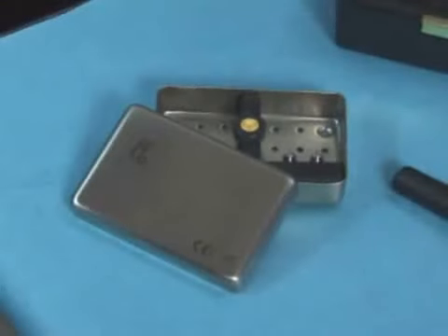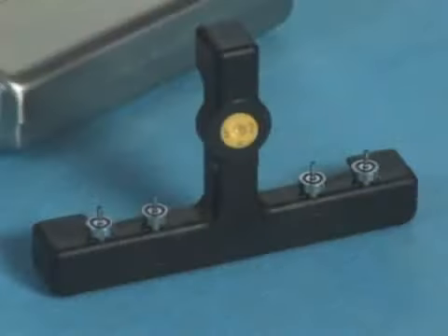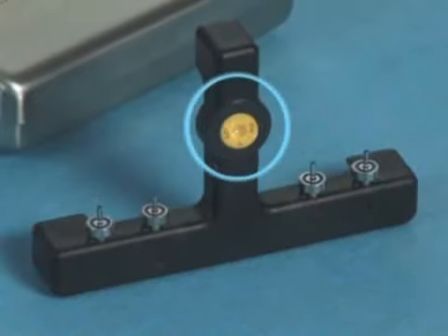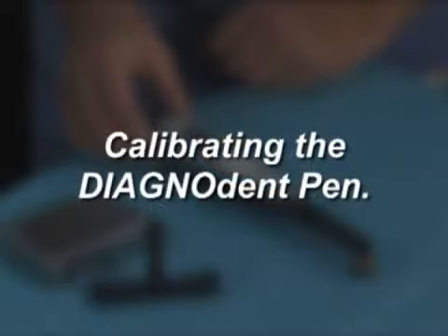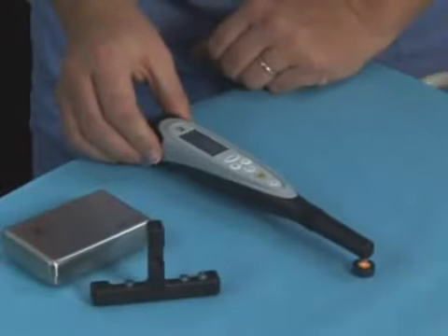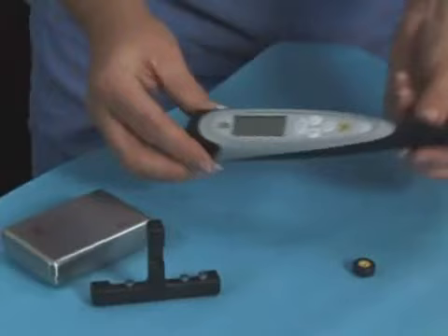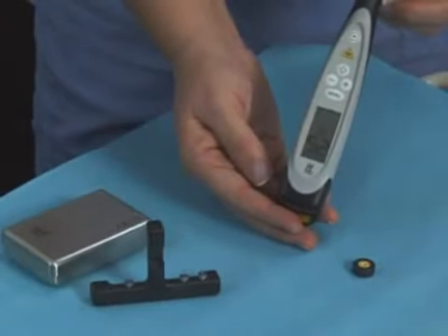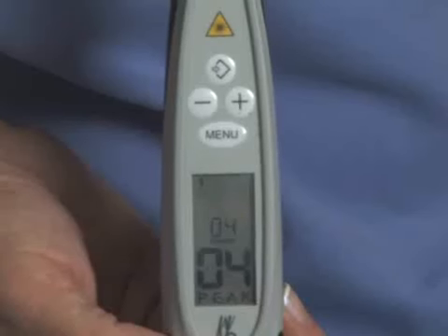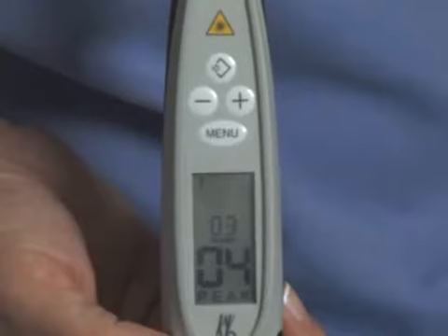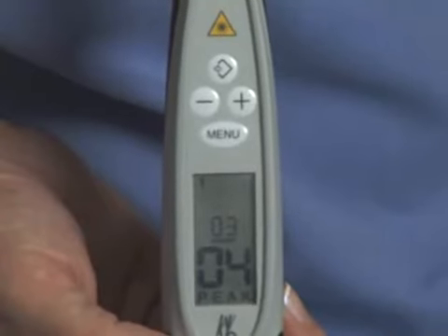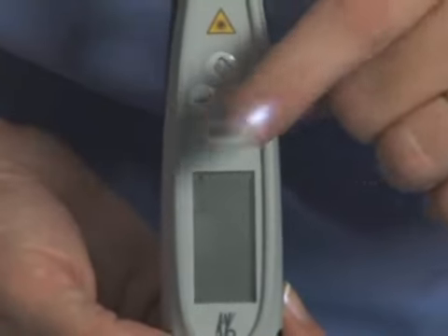Tips. The DIAGNodent pen comes with 4 occlusal tips enclosed in a sterilization cassette along with a calibration disc. Calibration. It is recommended that calibration be performed routinely with each probe tip change and before each new patient.